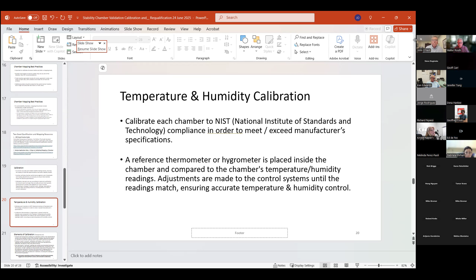There's some elements of calibration, comparing the temperature reading. This is set along the lines of a temperature one rather than humidity. Temperature reading of the calibration probe in the representative center of the chamber to get that chamber's display, adjusting the display to calibrate the chamber to get as close to the stated tolerance as possible. Then it gets a little bit more technical: provide a 3-point as found calibration verification. So the key there is 3 different points.